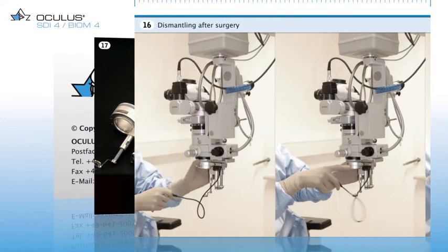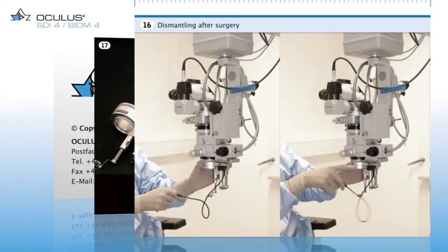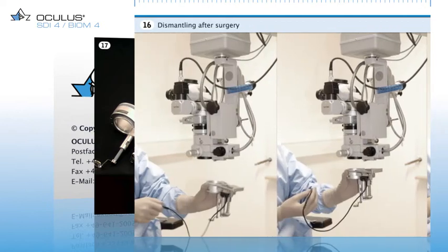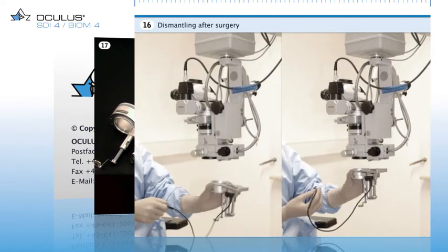After surgery, the BIOM has to be dismounted and prepared for storage. Here you see the BIOM 4C system being dismounted after an operation. Pulling on the cable sleeve unlocks the plug, which can then be easily disconnected. After releasing the knurled screw located on the side, the BIOM 4C system is completely removed from the dovetail mount. During disassembly, the BIOM components are placed on a table for further disassembly prior to cleaning and disinfection.